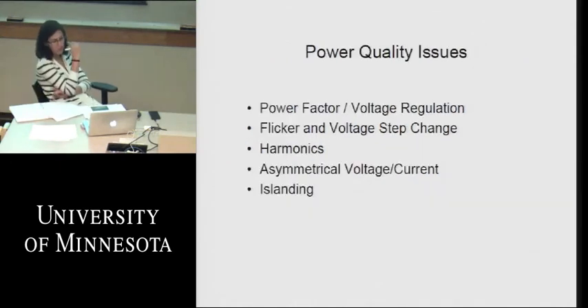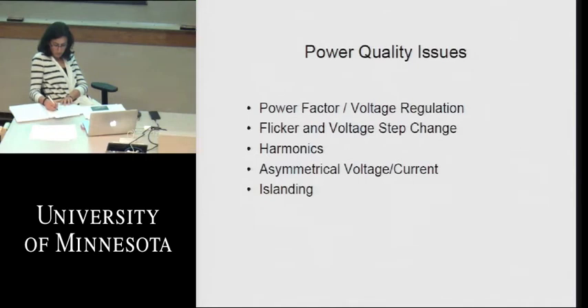These are just some of the power quality issues here. Power factor regulation that we talked about. Flicker, voltage step change. Flicker is voltage that is moving around a lot, and we'd like that to be absolutely minimal here. Each system can only take a certain acceptable voltage step change, 2, 3, 4%, generally dictated by what your voltage change is when you switch a capacitor bank in and out. We also have to look at harmonics and keep these to a minimum. Generally, wind turbines of old, the type 1 and type 2, produced almost no harmonics. So the more power electronics we put on to condition the output power, the more potential we have for creating harmonics that could be seen on the grid, and that's not a very good thing, and certainly there are limitations on how much of that kind of dirty power can be put onto the grid.